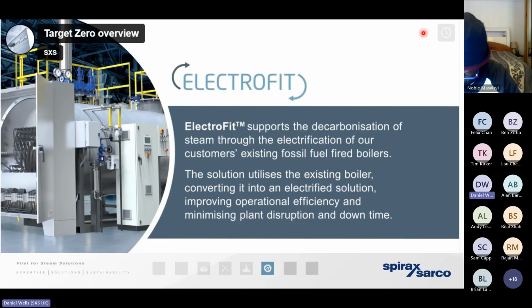So we could electrify our client's existing boiler, as we've mentioned. It's what we call an electrofit project. It really requires the boiler to be at the appropriate condition. So if the client's got a natural gas burner that's 4 or 5 years old that they want to decarbonize, then it's likely going to be in a good condition. But if the client wanted to electrify a boiler that was 20, 25 years old, it wouldn't really be commercially viable. They would potentially need to look at a brand new electric steam boiler as an alternative.